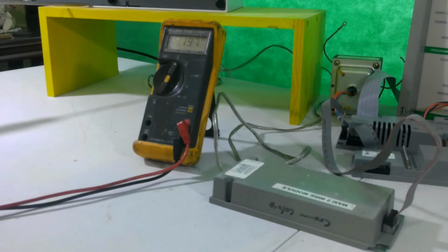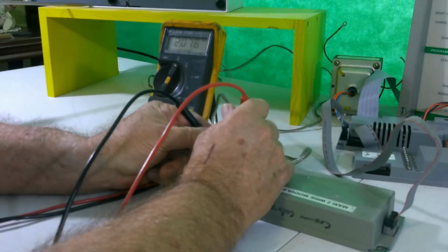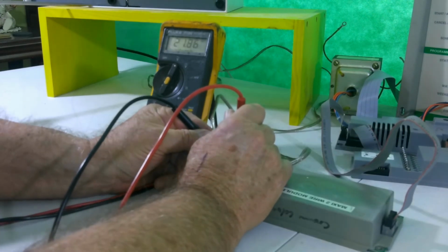Now we're going to look at the two-wire communication module, this piece right here. It's going to be located out in the satellite in the field. And it's either going to be located on the older units down inside the older style plastic pedestal, or on the newer styles, it will be found up under the face panel. What we want to check here is make sure that we have the correct voltage here. So we take one probe from our volt-ohm meter, and we put it on the input screw of the two-wire module, and we should see that same 21, 22 fluctuating voltage.